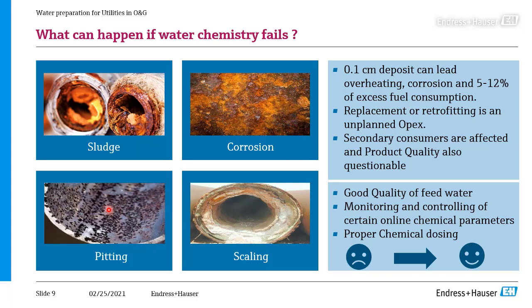And also here you have some pitting. So we need really to make sure that the water meets the quality criteria. And just some facts here. A 0.1 centimeter deposit can lead to overheating and corrosion, and 5 to 12% of excess fuel consumption. Just consider that has really a huge cost impact.